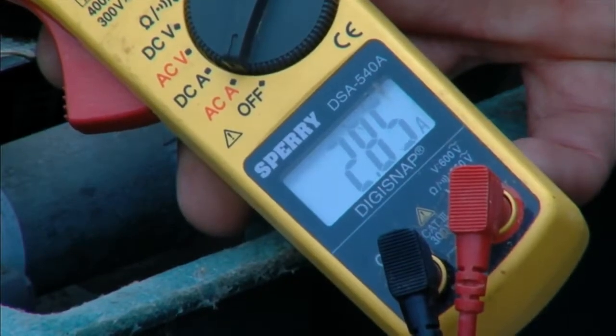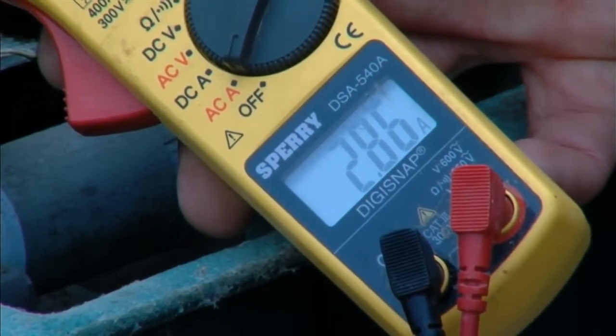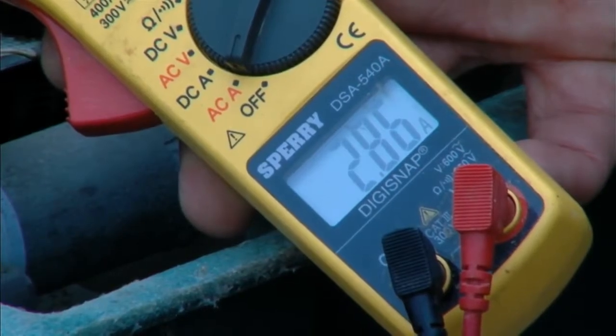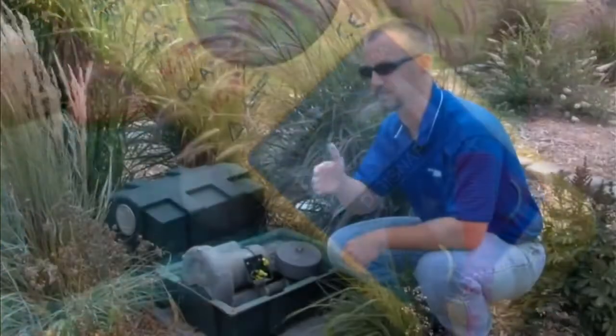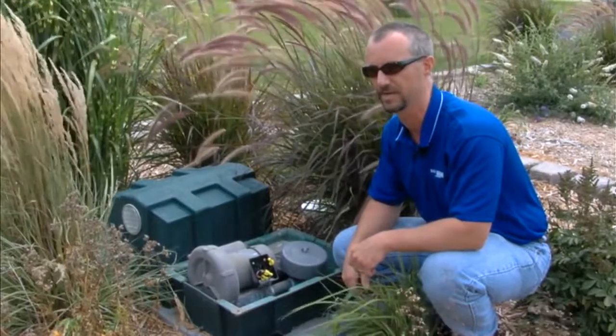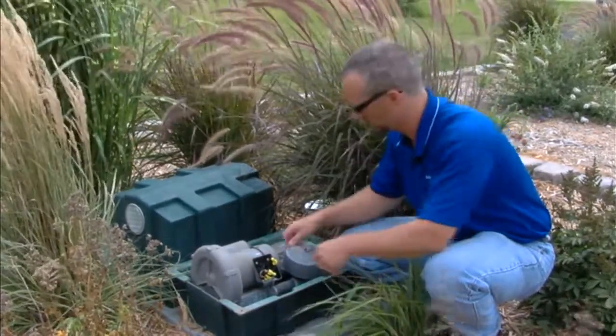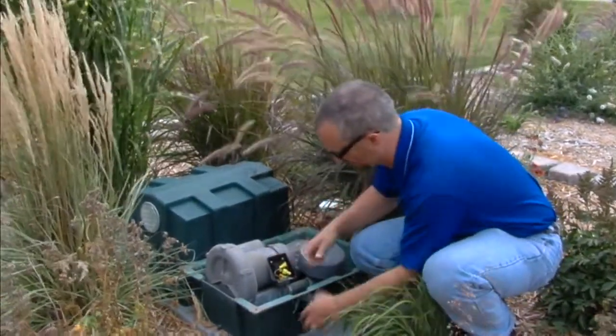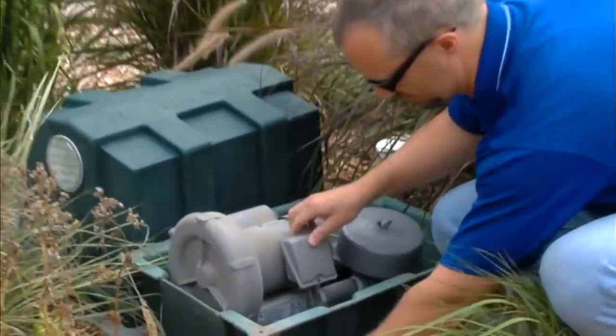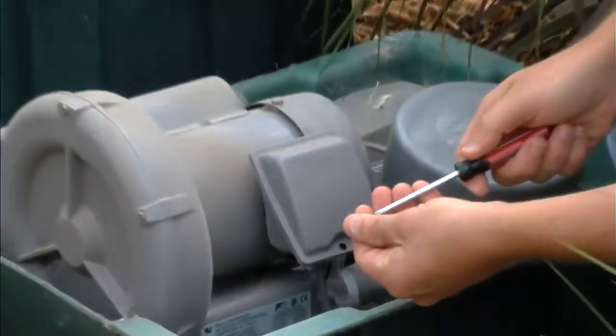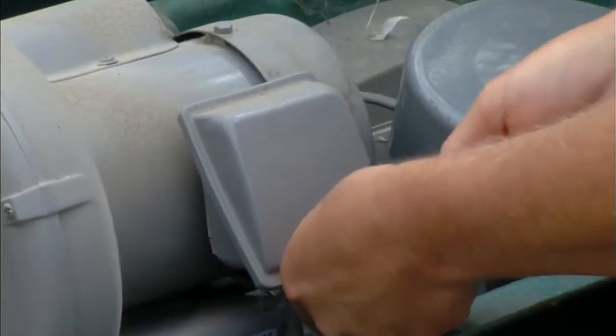Let it start up for a few seconds to get the full load. And we got our amp reading. Next thing we'll do then is shut the power back off after we're done taking our amp meter reading, so we can put our wires back in the junction box. Secure the junction box back in place with our Phillips screw.